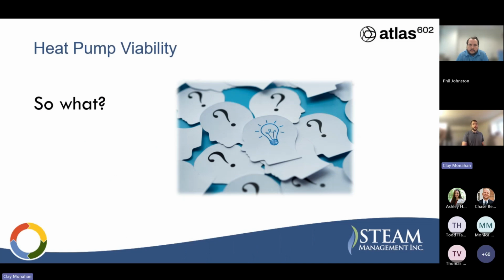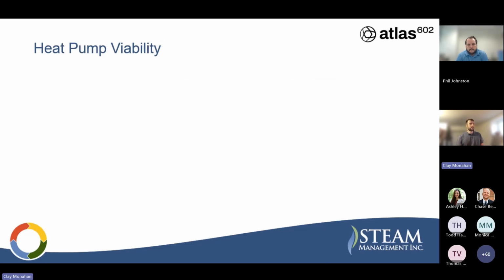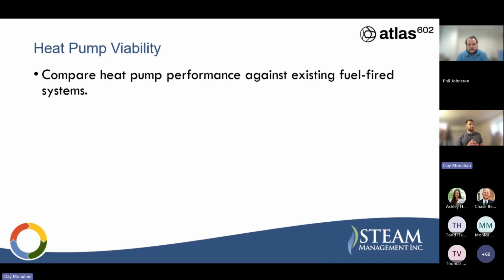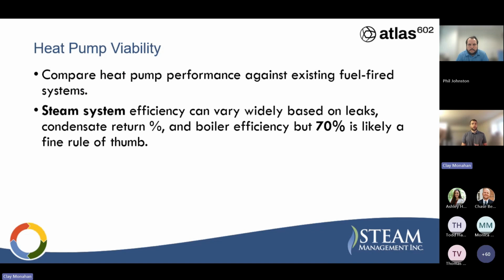Okay. All right, so we have theoretical COP, and we have that in mind, but what does that mean, and how does that actually affect project viability? Comparing heat pump performance against existing fuel-fired systems is really the metric that we're looking to beat. Steam system efficiency can vary widely, and a lot of attendees of these webinars can speak intelligently to this, but steam system efficiency can swing all over the place. For boiler efficiency, typically the rule of thumb is 83%, but between heat losses and leaks, the system efficiency of where that heat's actually delivered to an end user can be more like 70% or even lower. If we say 70%, you can use 65, I've seen that number out there, but 70% is a conservative number for a quick comparison between these systems.